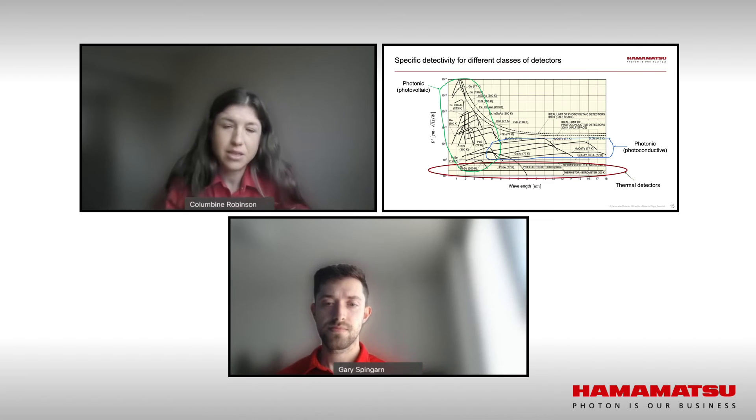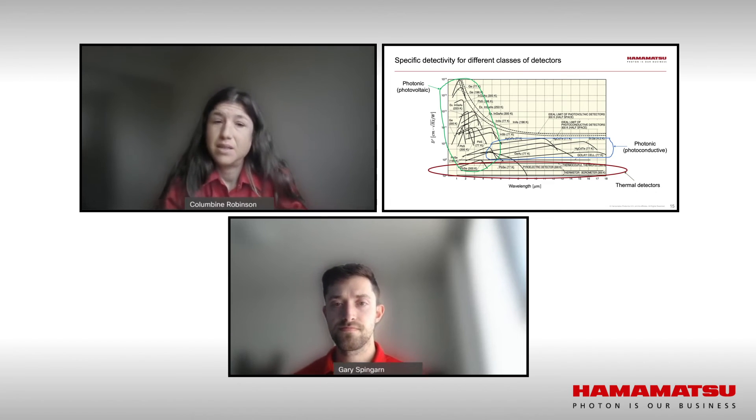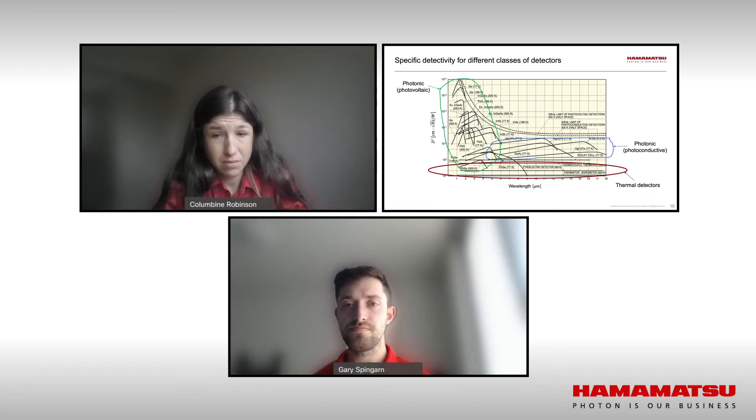One thing to note is that thermal detectors are cheaper. Now comparing photonic detectors: MCT generally have a higher d-star; however, we've seen a lot of unit-to-unit variability. If a customer is doing any kind of tool matching, this could lead to an overall hit in sensitivity. Additionally, they're quite expensive and therefore tend to have smaller active areas. Because of this, they are also no longer RoHS compliant.